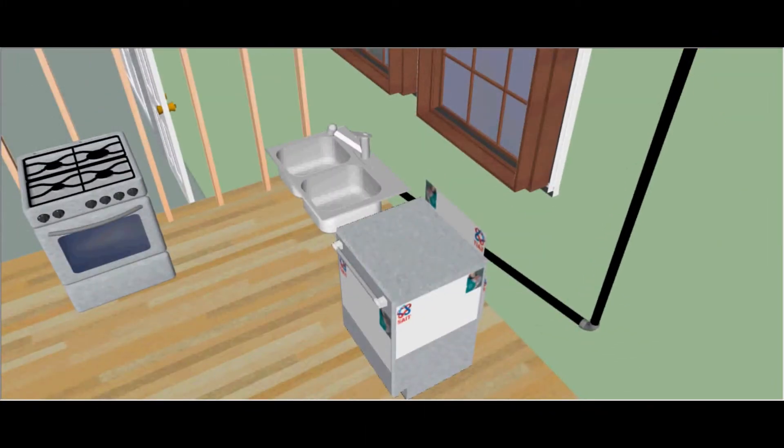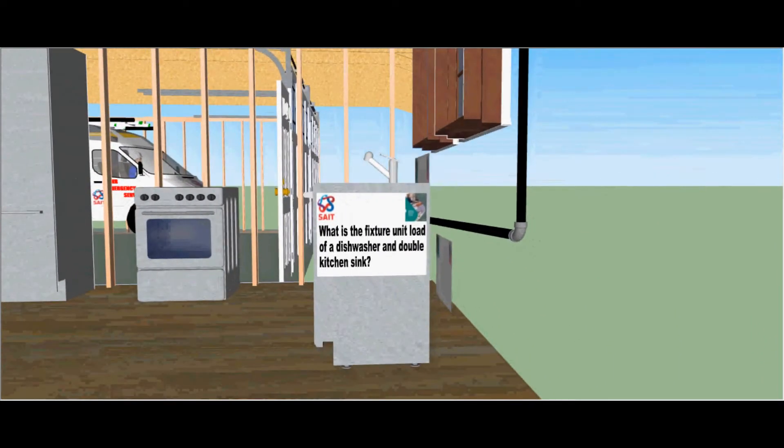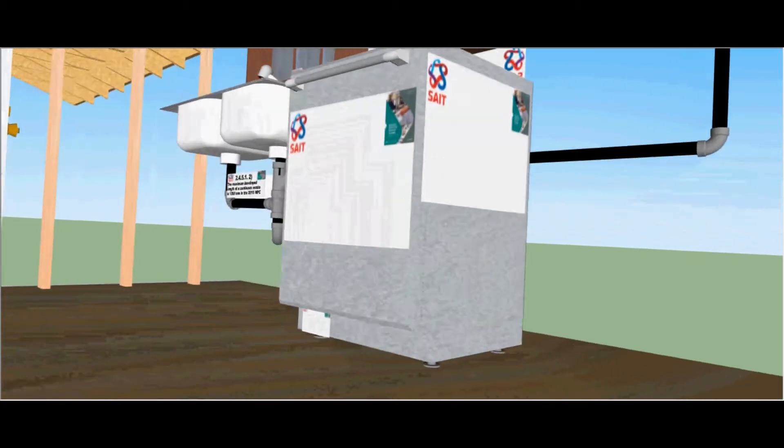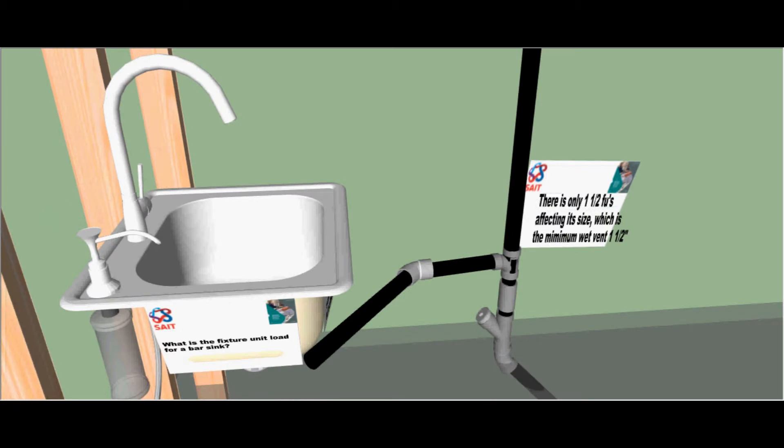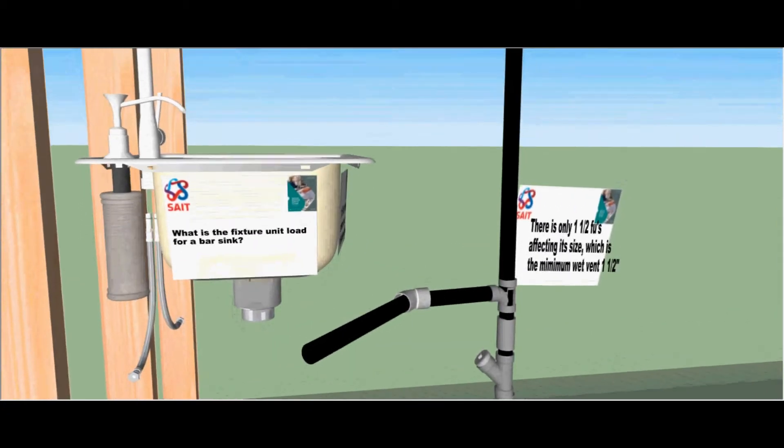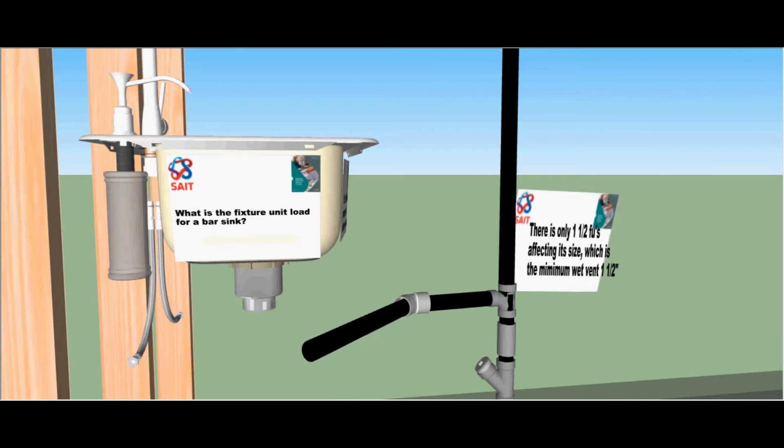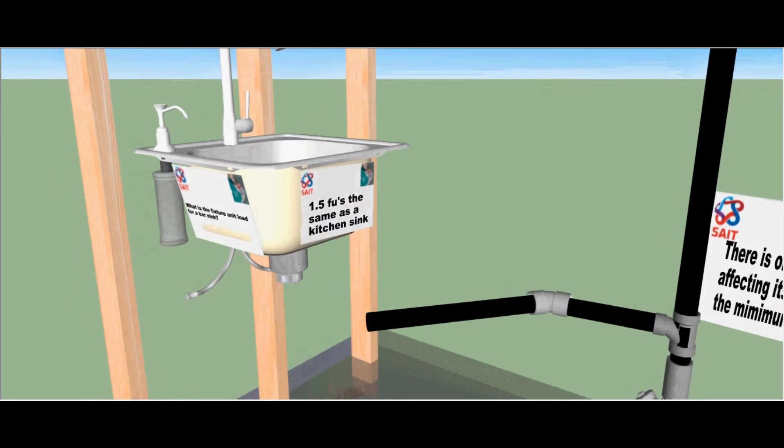Let's go down into the kitchen where we have a dishwasher and a double stainless steel kitchen sink. What is the fixture unit load for a dishwasher and a double kitchen sink? Only one and a half fixture units as they are used sporadically and not always at the same time. What is the fixture unit load for a bar sink? You can find it in table 2493 where it states that it is the same as a kitchen sink, one and a half fixture units.